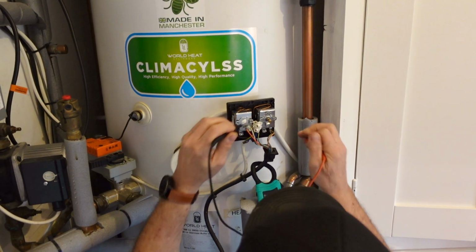The rads at the far end of the house, at the north end of the house, do not come to temperature. That I think is our biggest problem. Our COP is also something we're not hugely impressed with at 2.7. Obviously, everybody with a heat pump wants the highest possible COP number. Ken and I have gone around our system looking at the various bits and pieces that are associated with that.